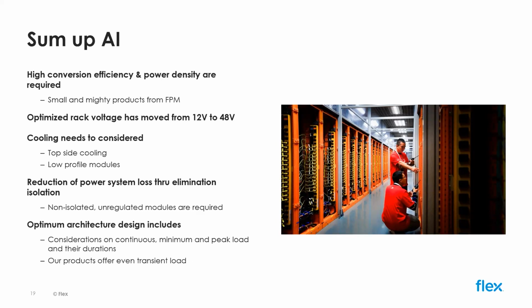And I don't think that's the end of it. As Ulla mentioned earlier, the power levels per rack are going even higher — 100, 200, even 400 kilowatts being touted at the moment. So we may even see the 48 volt transition in the future move to high voltage DC, like 200 volts, 400 volts, 800 volts. There's all sorts of potential movement in that area going forward.